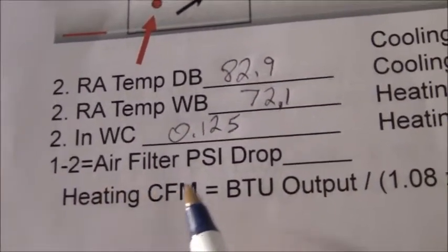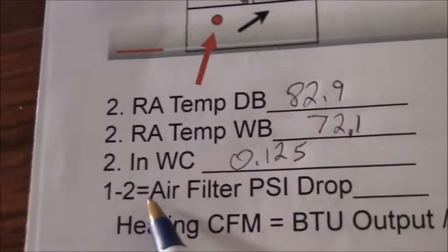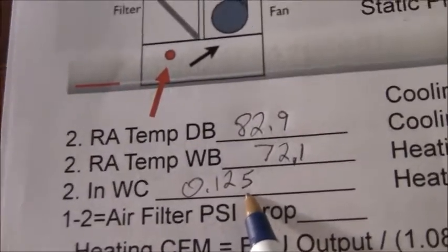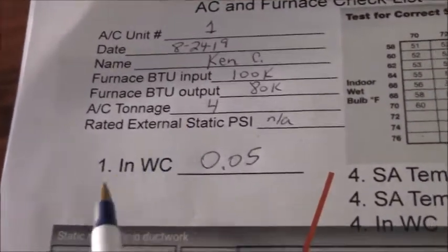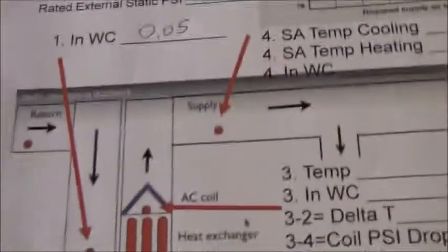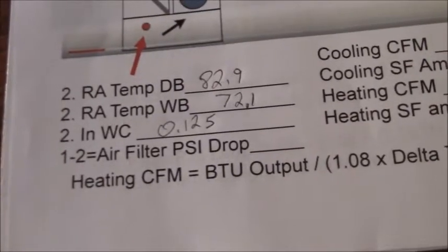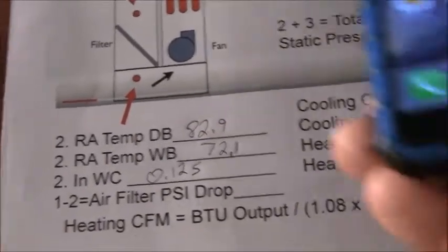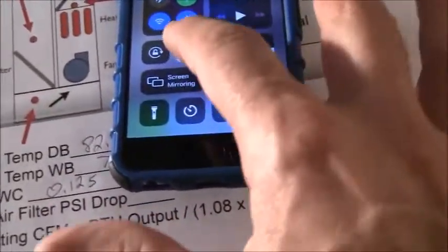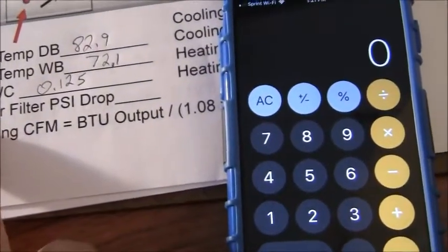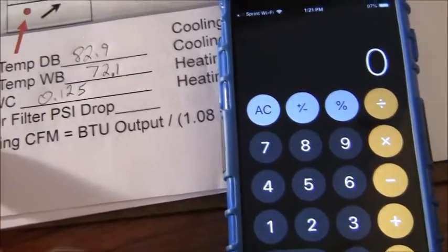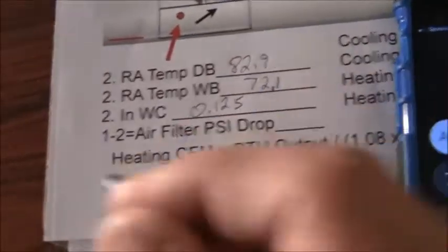Now, if we want to know the air filter pressure drop, we're going to take 0.125 and subtract it by number 1, 0.05. That is going to give you your air filter pressure drop. So let's go ahead and figure that out. So if I take my phone and go to calculator mode, clear that out, type in number, actually it should be 2 minus 1.